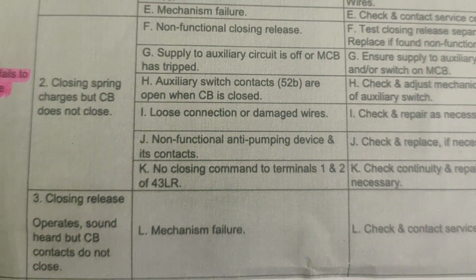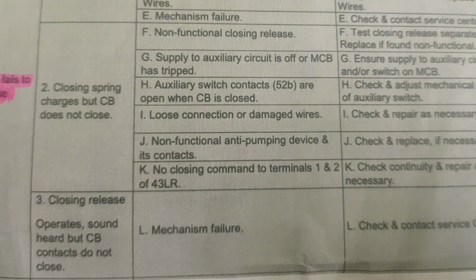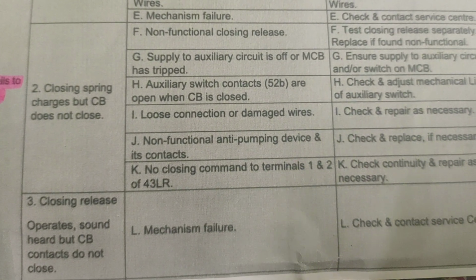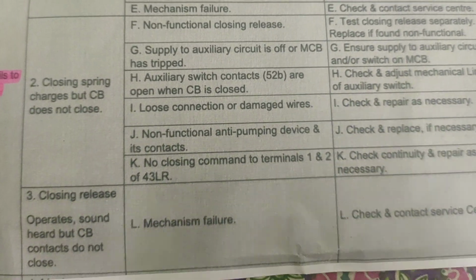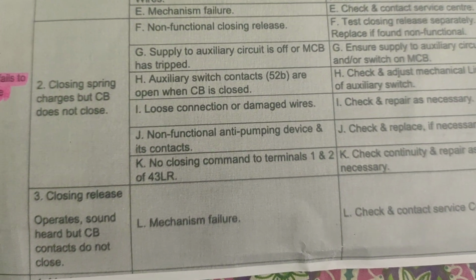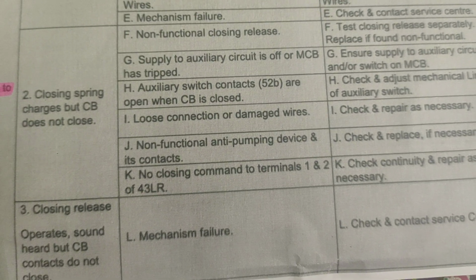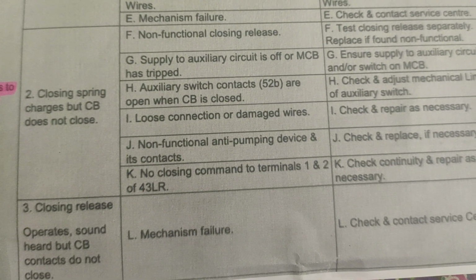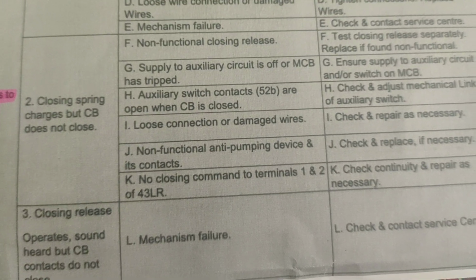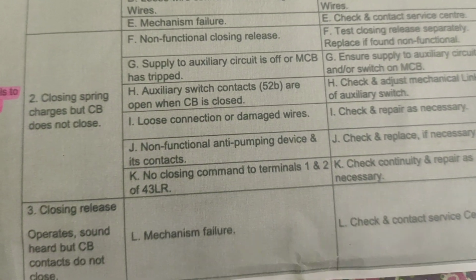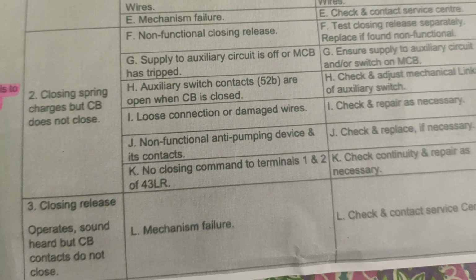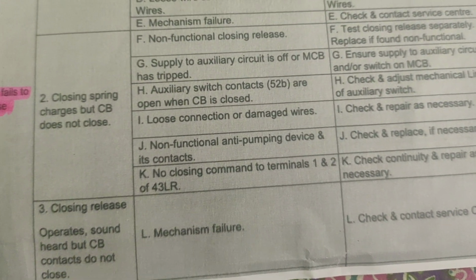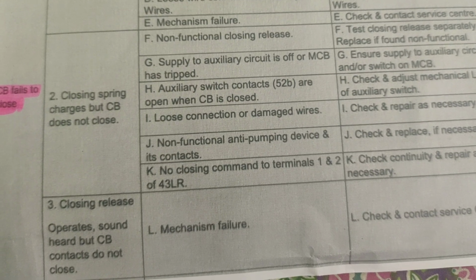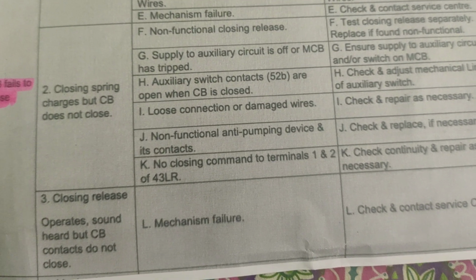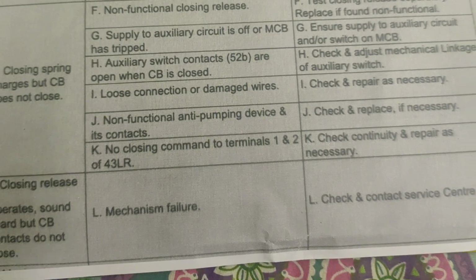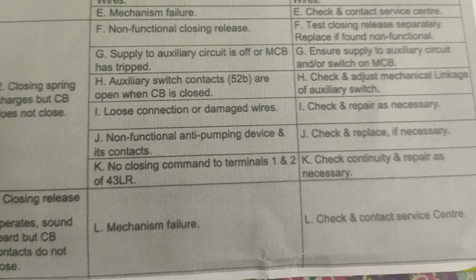The closing release, what will be the closing release? Operates, sound heard, but circuit breaker contact does not close. This is a mechanism failure. If there are mechanism failures, you have to check what types of problem are inside it, for your knowledge. But after that you have to contact the OEM, the original equipment manufacturer. The original equipment manufacturers will provide technical personnel for support, because they know what the problem is and how it can be solved, because they are the experts on that type of circuit breaker.